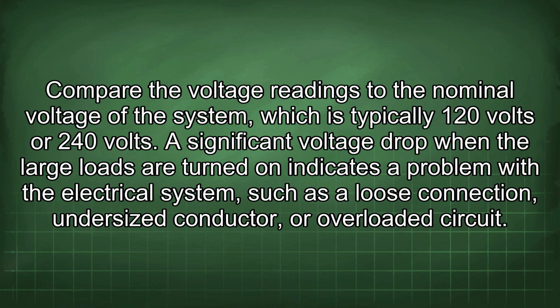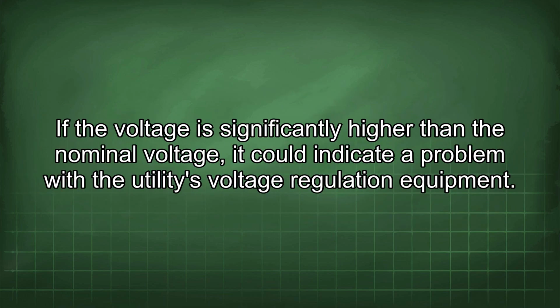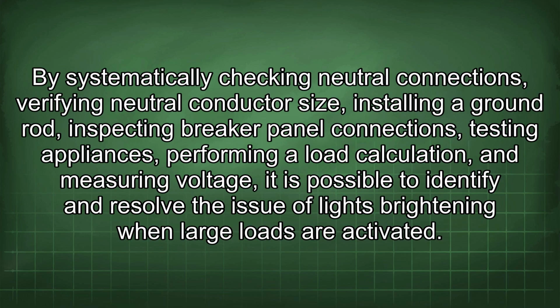A significant voltage drop when the large loads are turned on indicates a problem with the electrical system, such as a loose connection, undersized conductor, or overloaded circuit. If the voltage is significantly higher than the nominal voltage, it could indicate a problem with the utility's voltage regulation equipment.